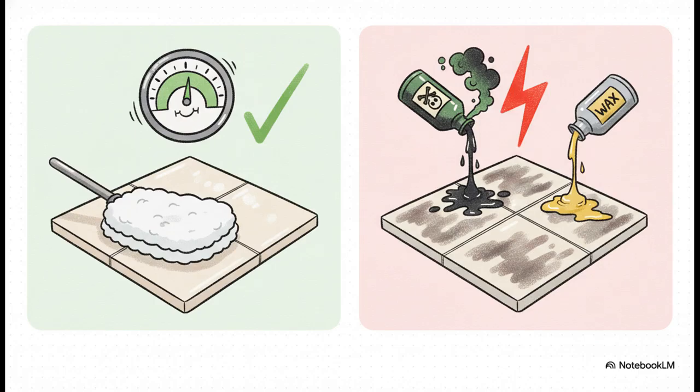On the flip side, avoid harsh solvents, acidic or high alkaline cleaners. And never, seriously, never apply wax. Just a simple film of wax acts as an insulator, and that will completely kill the floor's ability to drain static long before it even looks worn out.